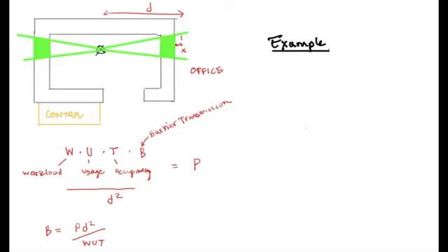And this is for a primary shield, so that's where the beam points directly at the wall. To figure out how big this area is, you just project the maximum field size of the linear accelerator onto the wall. So typically 40 by 40 centimeters. And then you have to look along the diagonal, and that's at isocenter, and then you project it onto the wall. And you can figure that out.